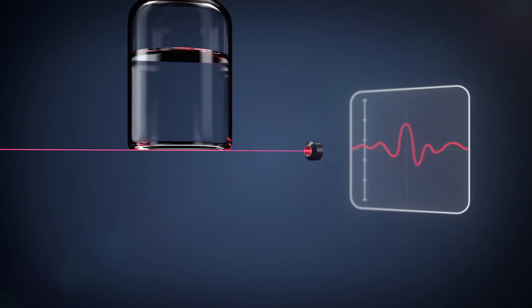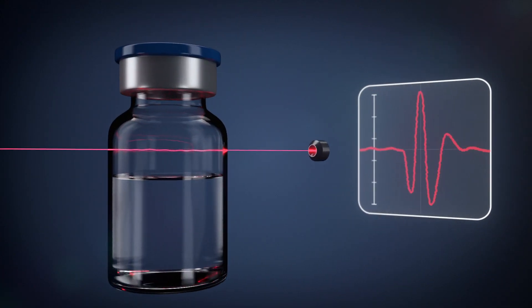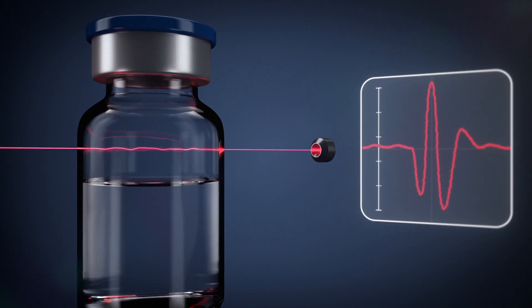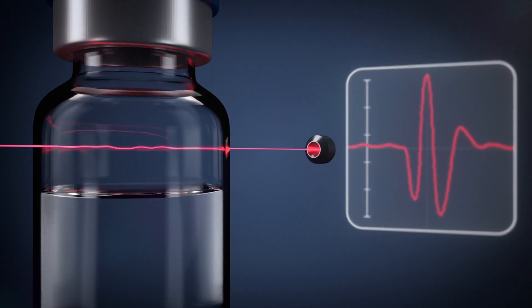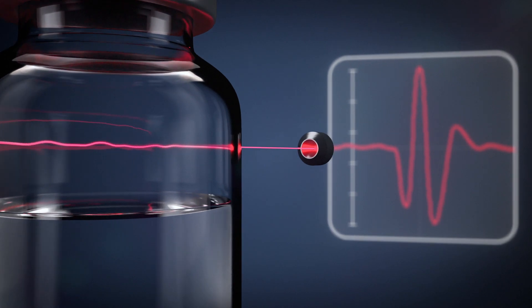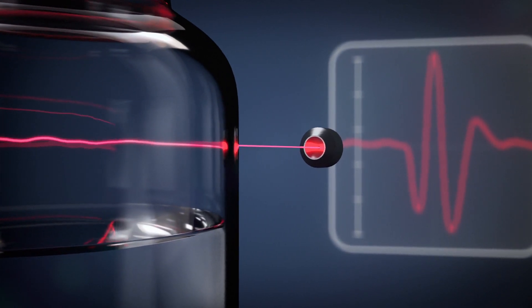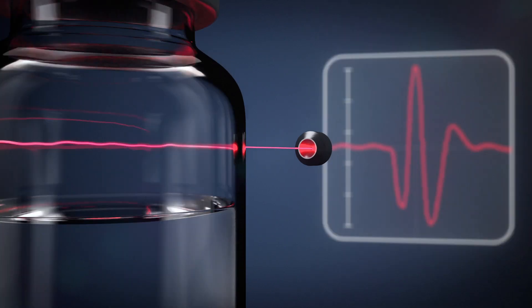The laser light is tuned to match the absorption frequency of oxygen. A detector measures how the light is absorbed as it passes through the headspace. Within seconds, the headspace oxygen levels in the sealed vial are accurately quantified.